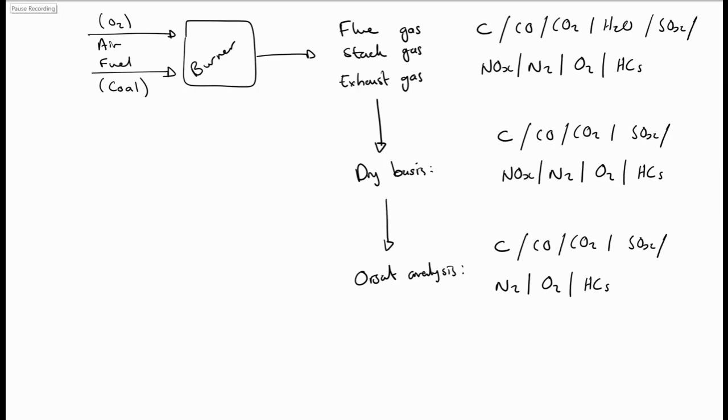We can also describe this exhaust gas in terms of an Orsat analysis. This is an analysis that we get from an Orsat piece of equipment or an Orsat analyzer. You get different types of these, but typically the Orsat analyzer does not give us any of the NOx coming from the system and also not any of the water. So it's the same components as before, but without the water and without the NOx. The Orsat analyzer was designed to distinguish between the CO, CO2 and oxygen leaving the system. That's what they mainly were used for, but you could also pick up the other components with this analyzer.